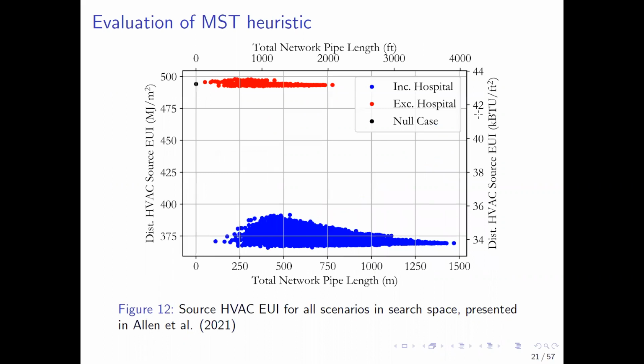This plot shows the district level HVAC source energy use intensity for all solutions as a function of network length. Again there's the same trend of bifurcation between scenarios where the hospital building is served by the network versus by independent systems. This bears out the trend of the hospital having lower source EUI when served by the district network, and its significantly higher EUI and loads drive that result for the network as a whole. It's worth noting the null case exhibits the highest source energy use intensity for HVAC.